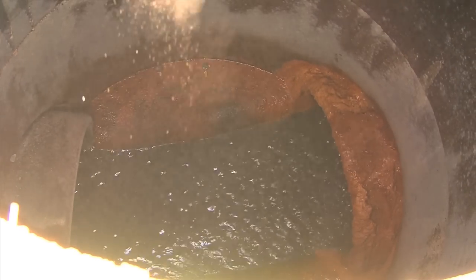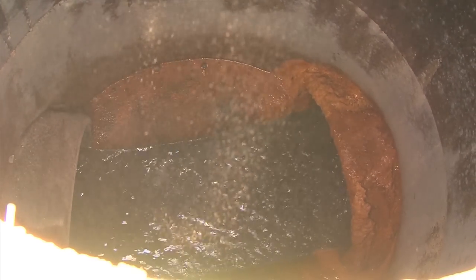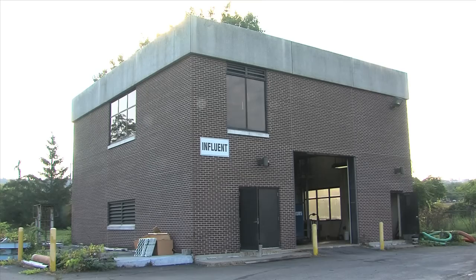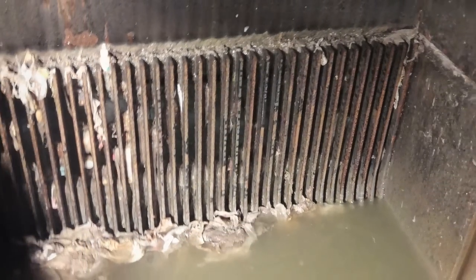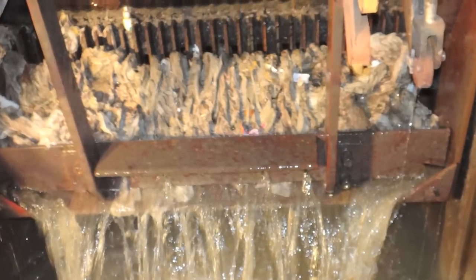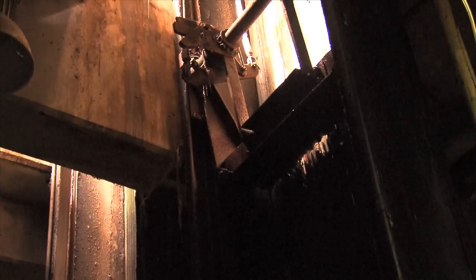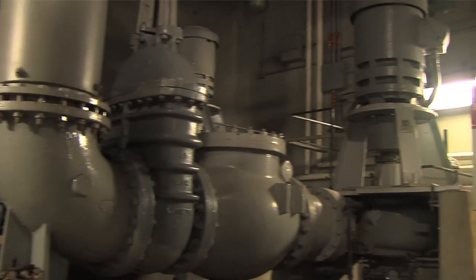This is a trunk line close to the plant. Though the amount of flow right now is fairly low, the pipe diameter is large and far underground. In the influent building, the wastewater passes through a fence of metal bars spaced an inch apart. This bar screen catches large debris — mostly rags, sticks, and rocks — which could clog up the pipes and pumps. The waste caught by the bars is raked up, lands in a dumpster, and goes to a landfill. This initial removal of material that can cause problems is called preliminary treatment.